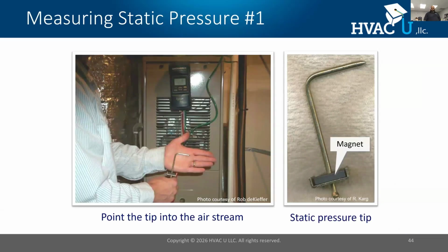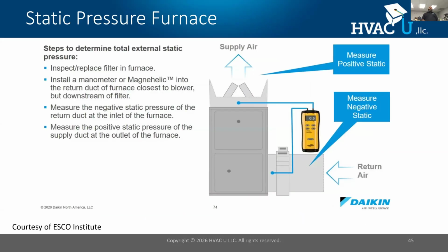Let's talk about static pressure. Static pressure is bursting pressure. I like to call it a proxy measurement. What static pressure is, I am able to measure the bursting pressure of the ductwork, and that gives me an indication of airflow. How static pressure works: if my static pressure is high, my airflow is lower. And if it's high and my airflow is lower, I could get to the point where I can start tripping out on temperature limit.